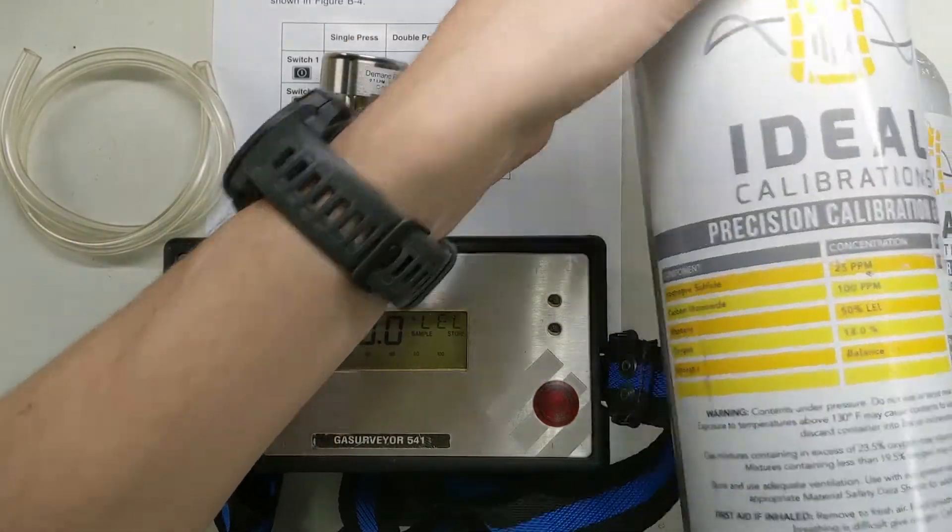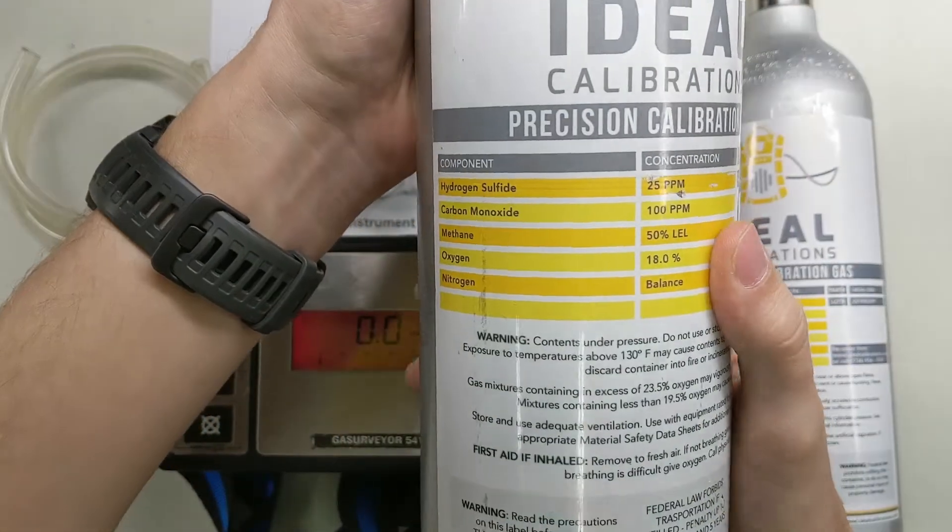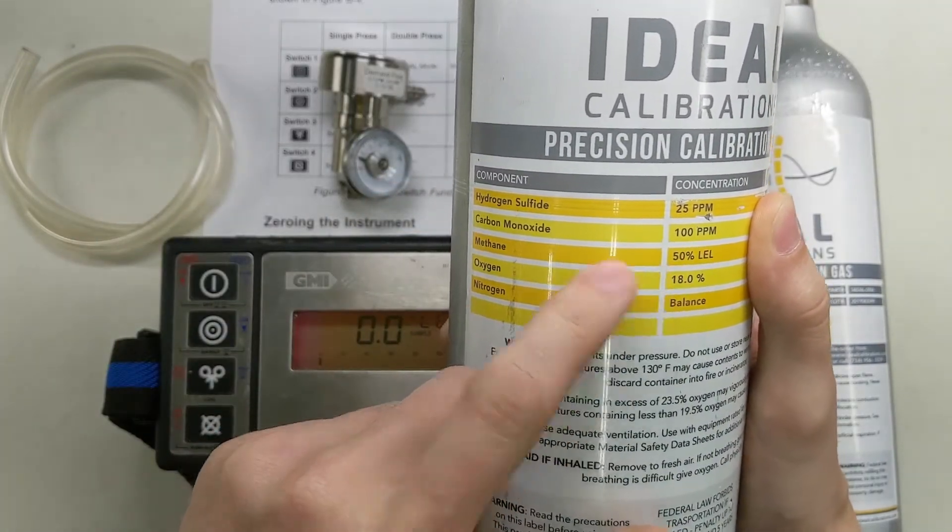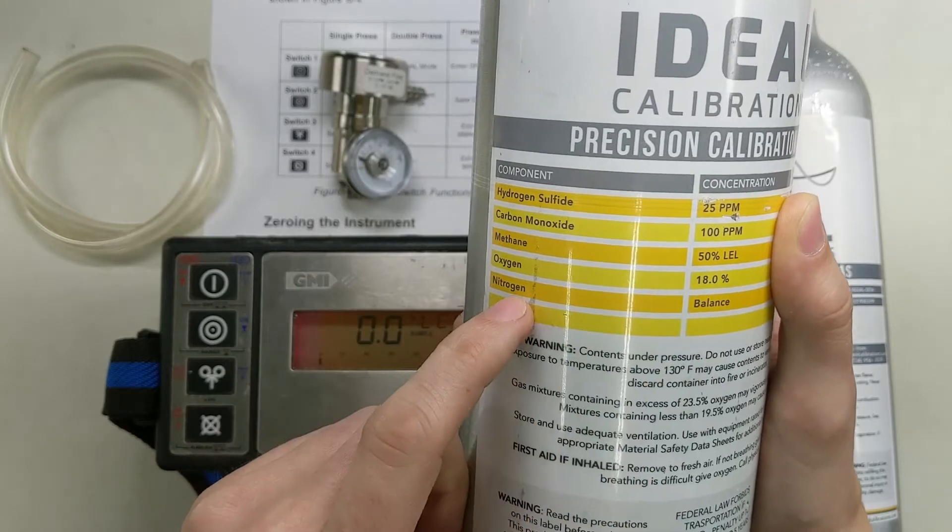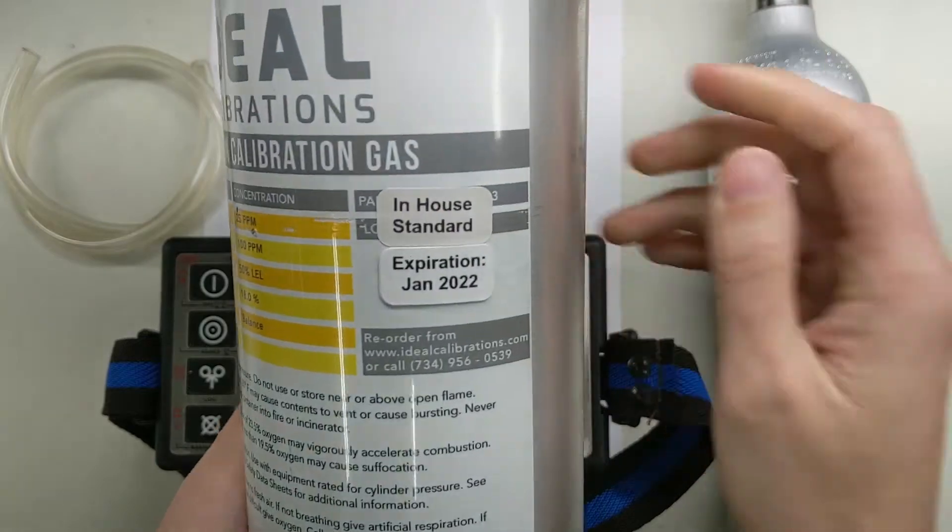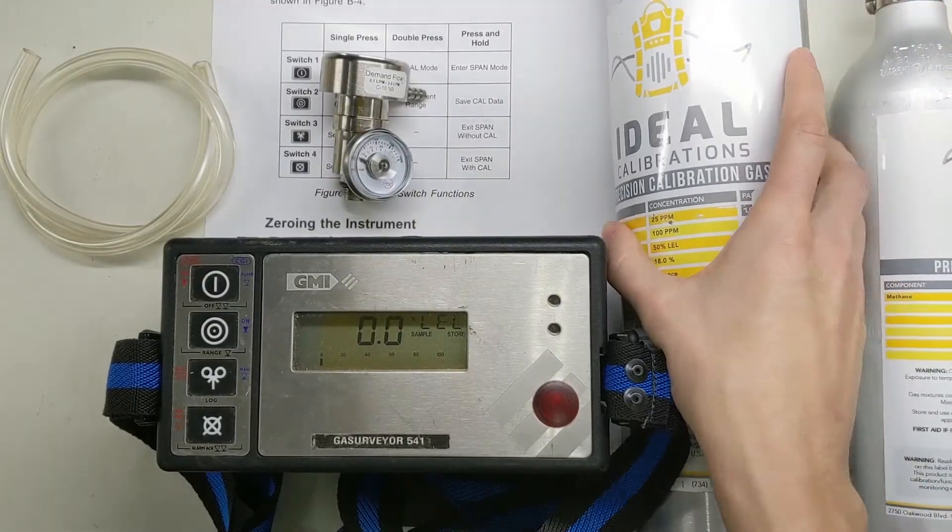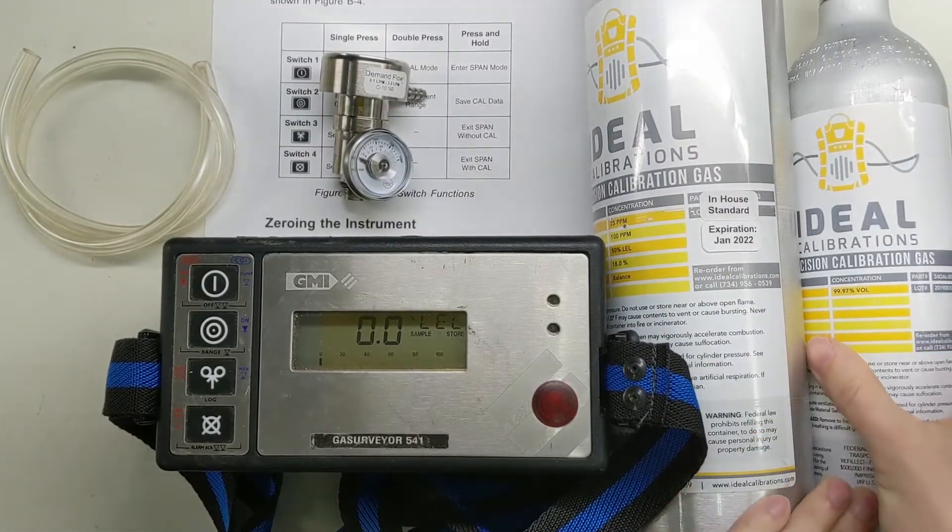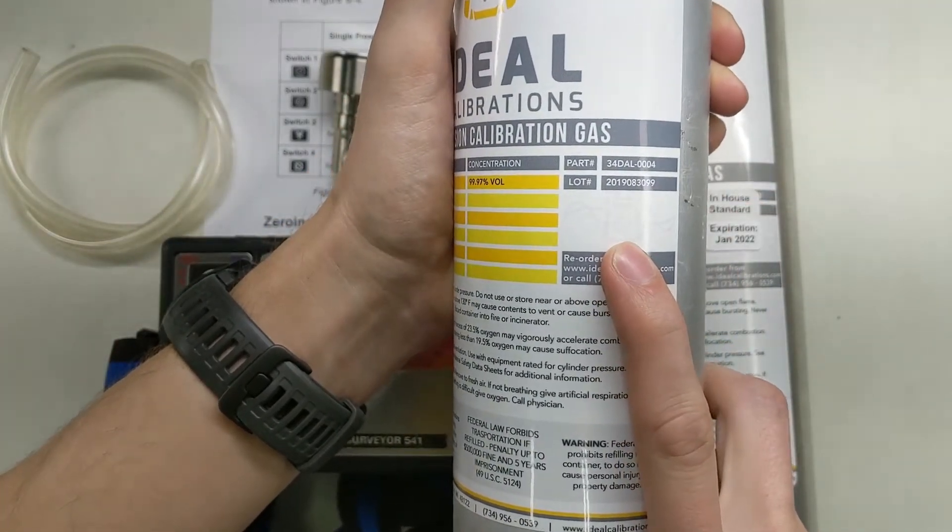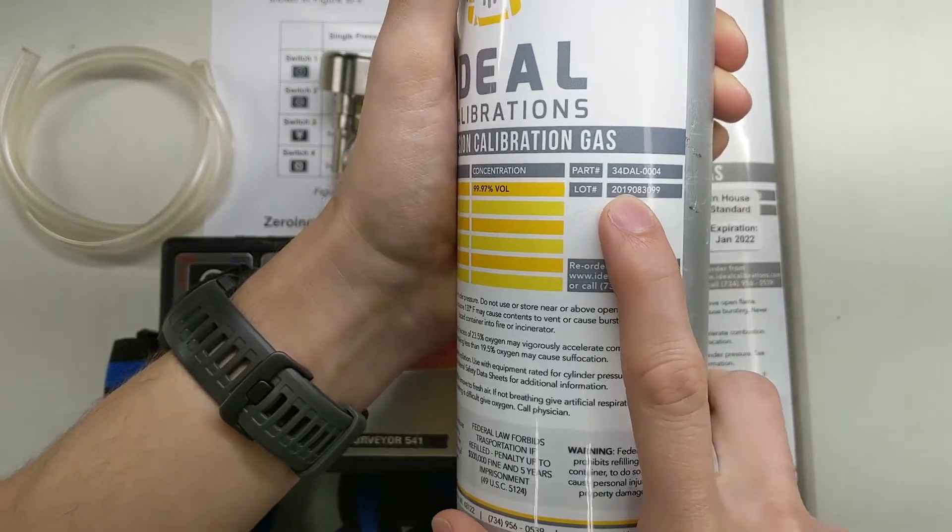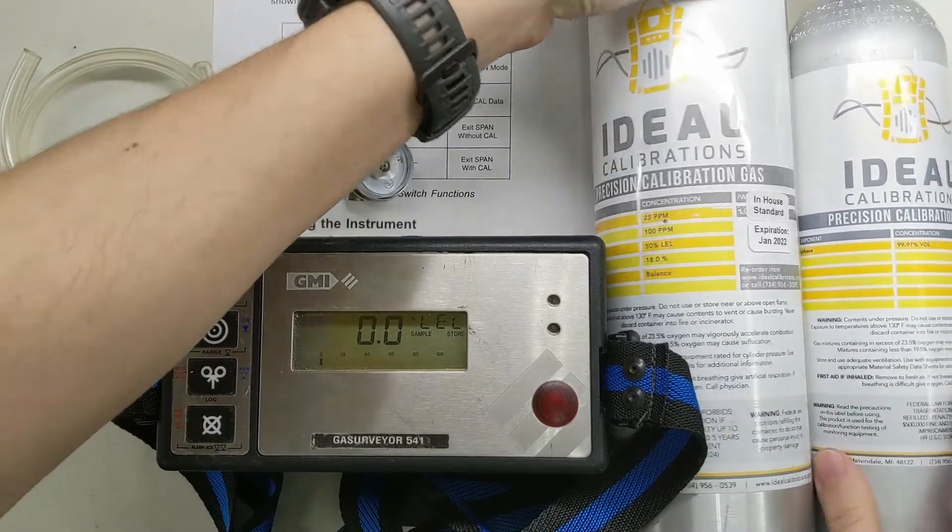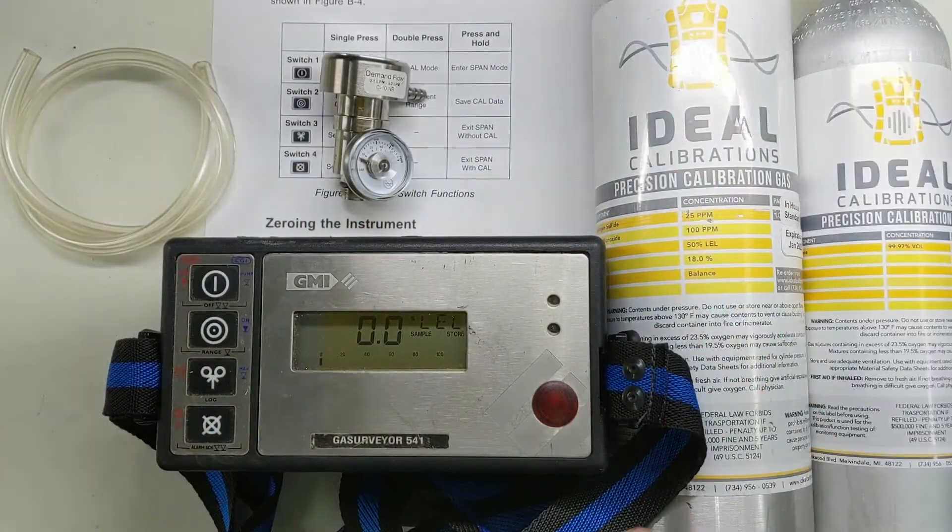Down here we've got another cylinder. This is 25 parts H2S, 100 parts CO, 50% LEL methane, and 18% oxygen with nitrogen balance. Check our expiration date and we are good to go. This one is well within expiration as well.